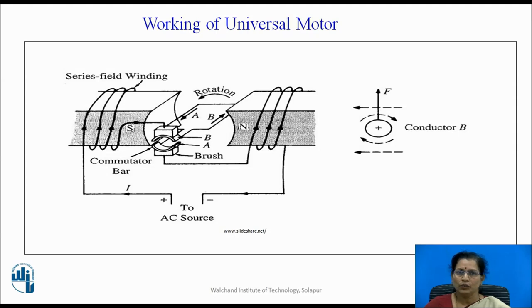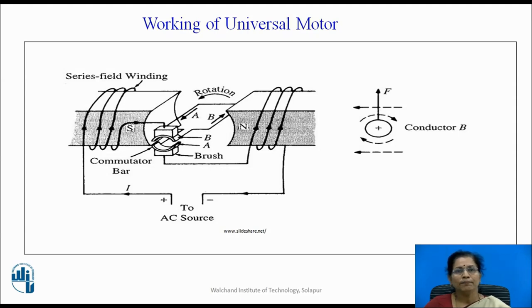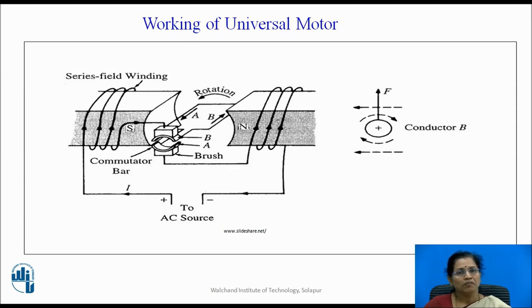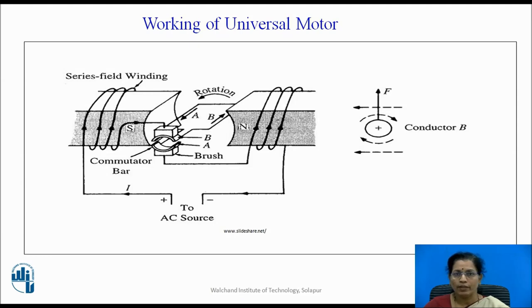Now let us discuss about the working of universal motor. You can see in this diagram the series field winding creates the magnetic field, with N and S poles created by using that winding. The armature conductors are connected to the commutator through brushes, and we can connect AC supply or DC supply. If we connect DC supply for this motor, the working is the same as the DC motor. Whenever any current carrying conductor is placed in the magnetic field, a mechanical force is created on that conductor. We can find out the direction of the force by using Fleming's left hand rule.